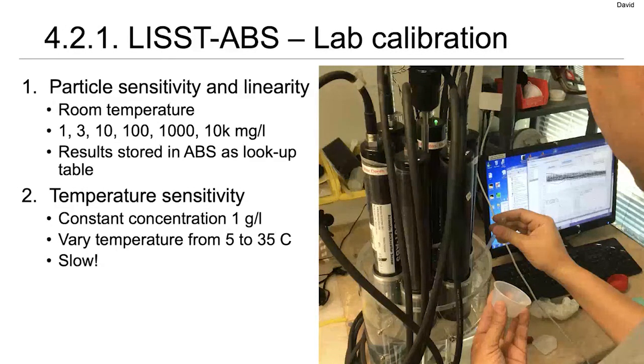I remark that this is slow because we're heating a not insignificant amount of water, and also because it does take time for the instrument itself to track the temperature of the water. So it's a process that takes at least a few hours. Again, we do that on batches of 6 instruments at a time. The results of the temperature calibration are fitted to a polynomial, usually a second order polynomial. When the instrument is deployed in the field, it has the lookup table, and it has the polynomial coefficients for the temperature calibration in its memory. And it applies those in real time when it makes its measurements.